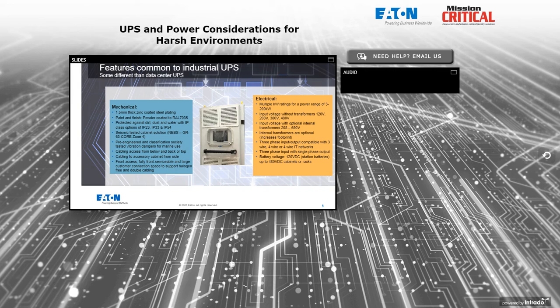Now, what about electrical requirements? Different kilowatt ratings within a product range, so the UPS is rated and matched exactly to the power requirement that the client intends. Voltage, even without transformers: typical voltages we see in this part of the world are 120, 208, 380, 480, and of course 600 volts up in Canada and in some cases here in the US. And with optional internal transformers for both input and output, the ability to go as high as 690 volts for the input to that UPS is typically required.